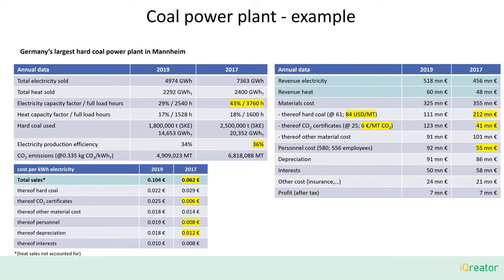Since we were a bit puzzled about the low utilization rate and the high overall cost, we were looking into a comparison to the numbers of previous years. Here we have a one-to-one comparison of the situation in 2019 and 2017. Overall, the electricity capacity factor was considerably higher in 2017 and also the production efficiency. Although the cost for coal was higher in 2017 with 84 US dollars per metric ton, the overall cost was much lower, being around 6 cents per kilowatt hour. The main contributors are on the one hand the CO2 certificates that were trading at only 6 Euro per metric ton in 2017. But also, everything that is fixed cost like depreciation, personnel, maintenance, etc., is naturally contributing less if the plant is running at a higher capacity factor.